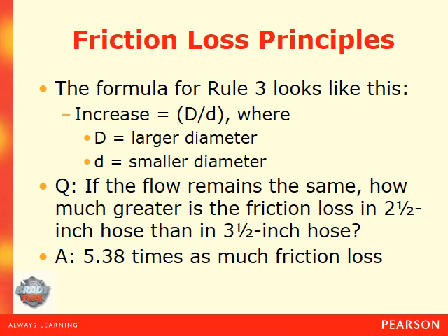So if the flow remains the same, how much greater is the friction loss in 2.5-inch hoses than in 3.5-inch hoses? And your answer would be 5.38 times as much friction loss.